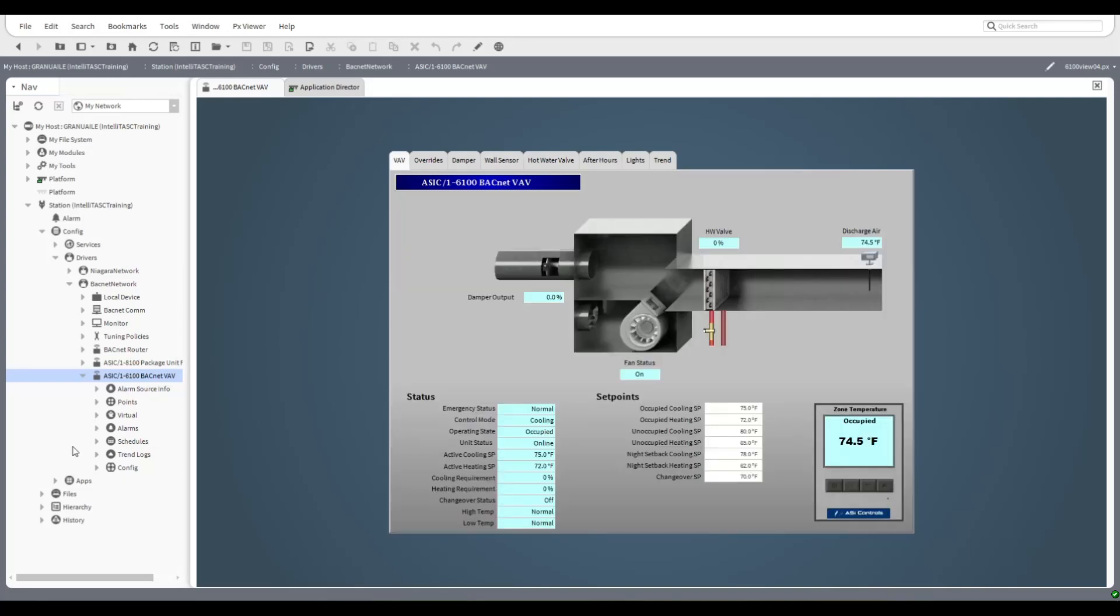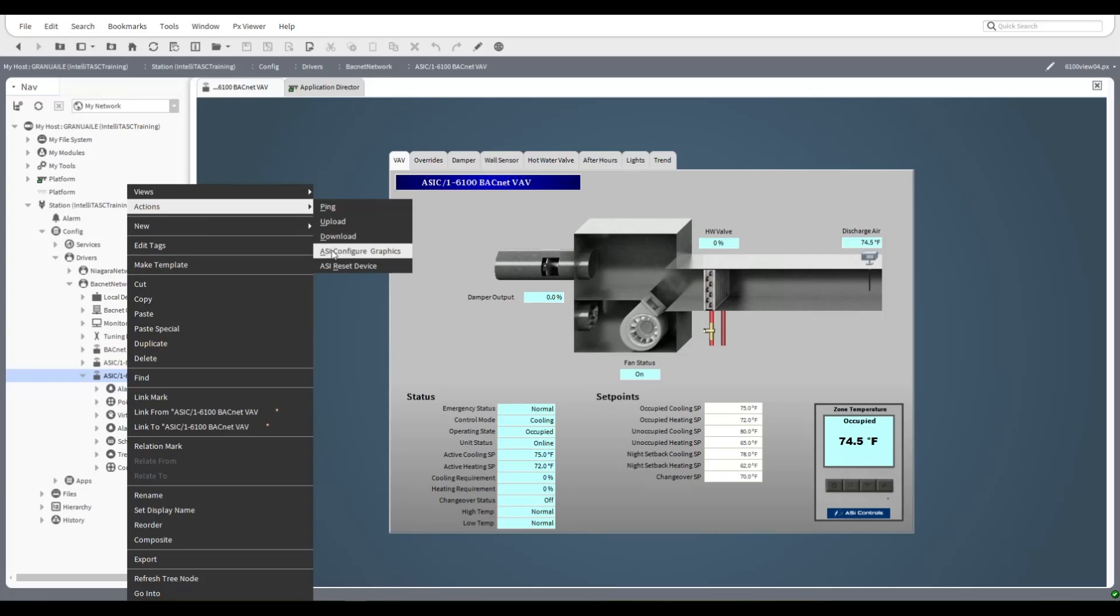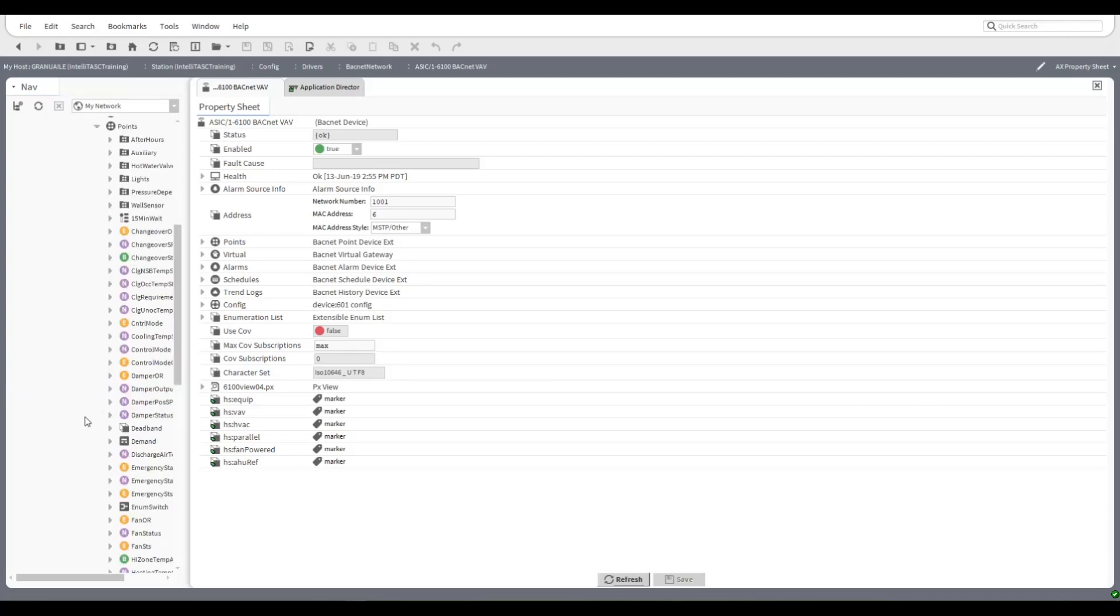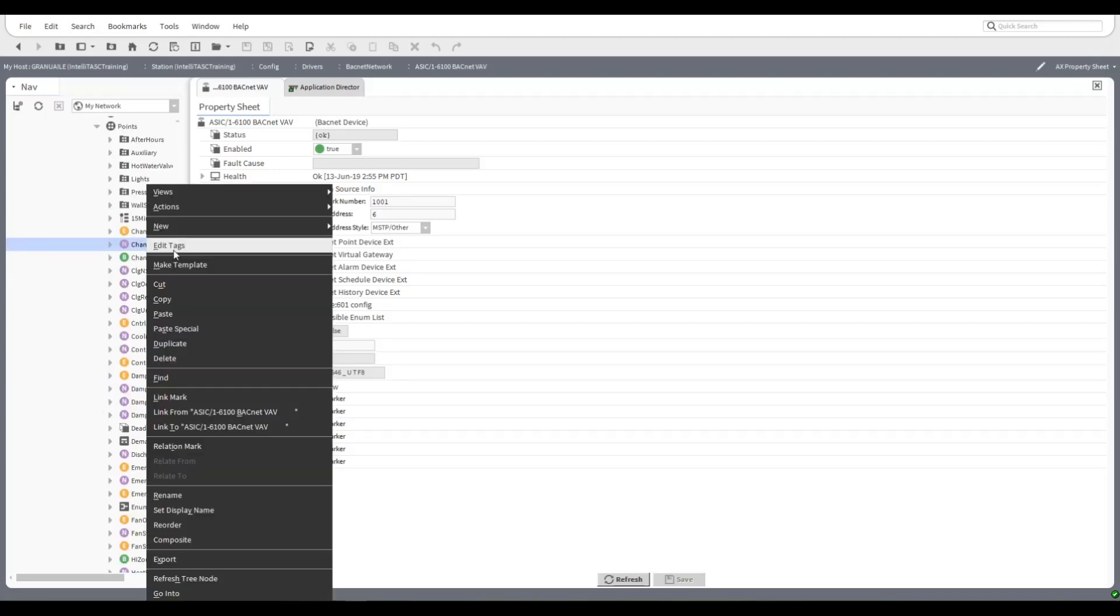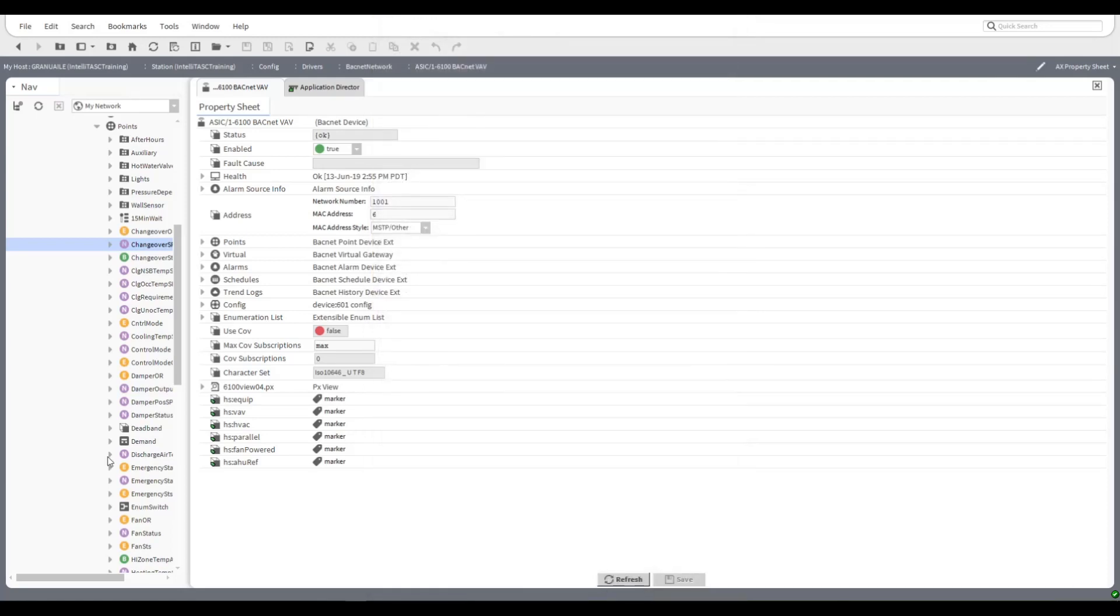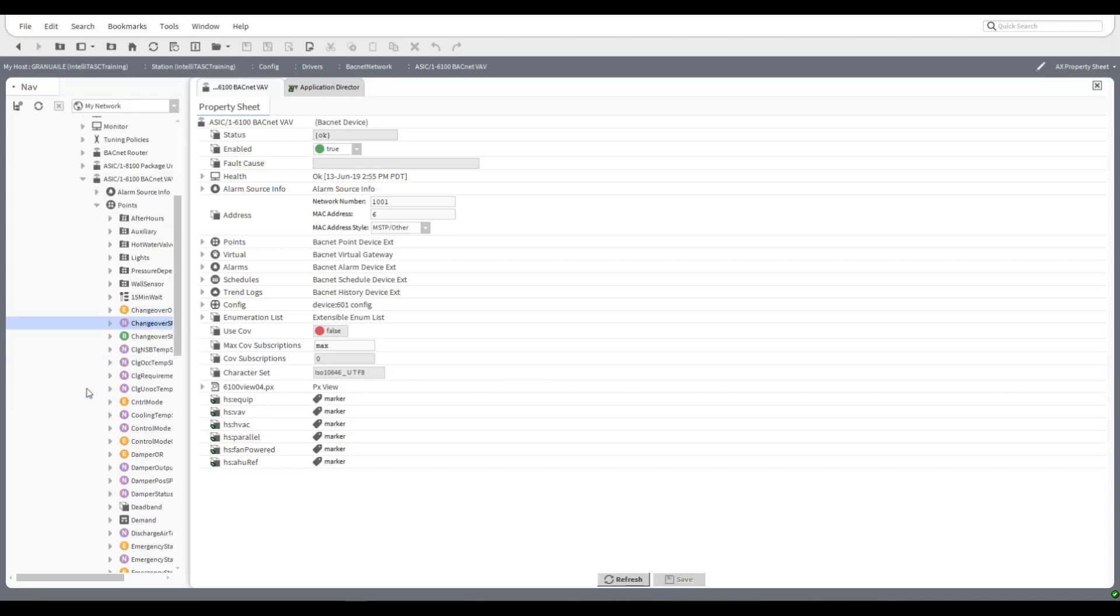Just a quick few things additional about configuration, some features that you get in addition to what we've already discussed. If you right click on the device and go into its properties you will find haystack tags attached to the device. The device gets tagged automatically with haystack tags as do the points. If you go into the points you will see the tags here as well and so without having to do anything you actually have everything tagged up haystack style if that is of use to you. Now in order to get the haystack tags working of course you need to ensure that the haystack module is loaded on your system as well.